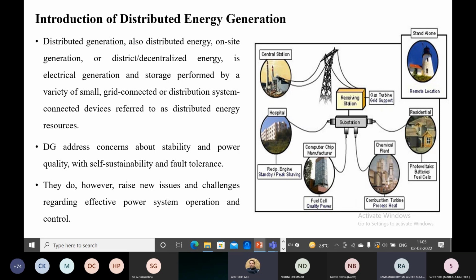As somebody was discussing, bidirectional flow is possible. Suppose you are connecting your generator to the grid, then the possibility of reverse power flow is always there. You have to control it by installing protection devices or specific power flow control devices. But if the system is working in standalone mode, there is no question of reverse power flow, because your generator is a less inertial source and your load is only consuming power - there is no generation from the other end. That's the flexibility of standalone distributed energy generation.